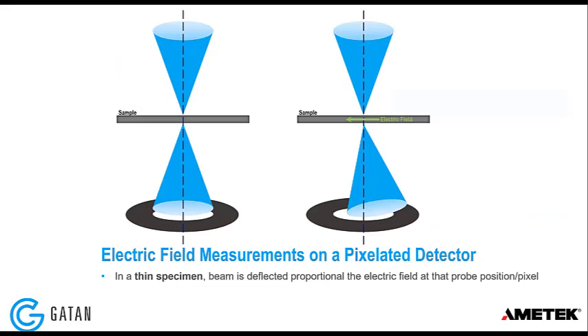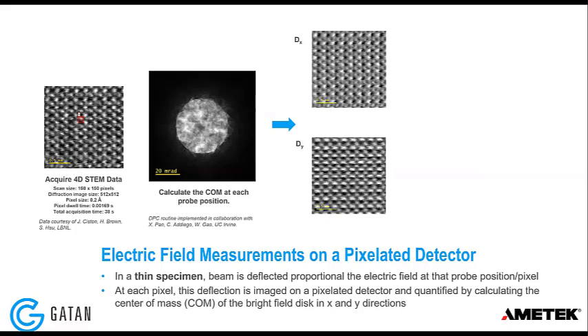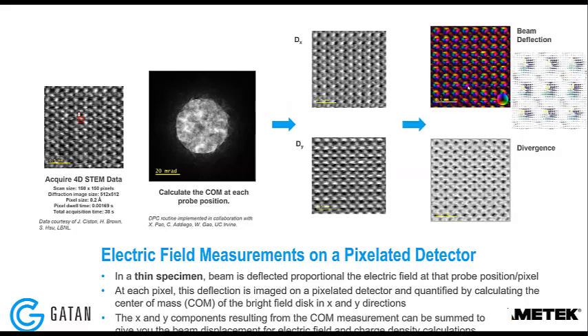The third analysis type is differential phase contrast imaging. If you have an electric field in a thin specimen, the beam is deflected as it passes through. By measuring this beam deflection using a large convergence angle, measuring the center of mass shift, you can calculate the beam deflection and divergence, and from those calculate the charge density and electric field in the sample.